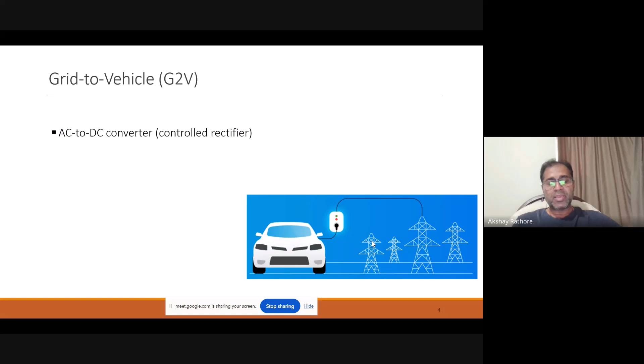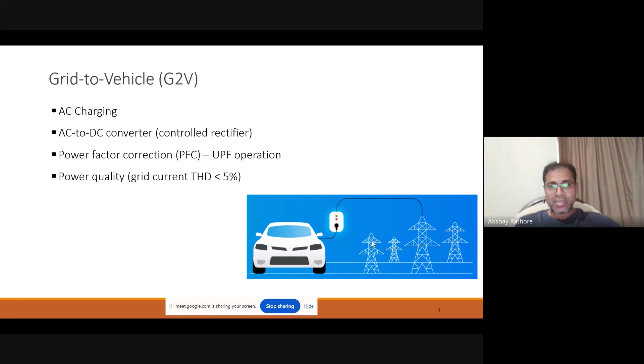So this is the requirement: power factor should be unity if it is a grid to vehicle charger, and power quality of the grid current should be quite high, meaning total harmonic distortion should be less than 5%. Another requirement is that none of the harmonics should have a distortion value more than 3%. So total should be 5%, and any harmonic component should not exceed 3%. These are some IEEE standards, and all the chargers or products in the market should respect these standard guidelines.